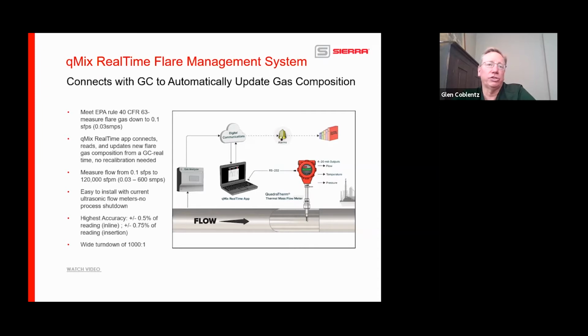We've got 5 or 7 of these full systems up and running in the United States. They're all being used in conjunction with multipath ultrasonics, because those things are expensive and the refineries aren't just tossing them out. When you're looking at this system, you basically have a device on site that creates, via Modbus, whatever the composition is. We need to know the percentage composition. That comes through the digital communications, goes into custom Q-mix software that's developed and written for each unique application. Then that is connected to the 640i, and the new composition can be put into the meter as often as every 30 seconds.